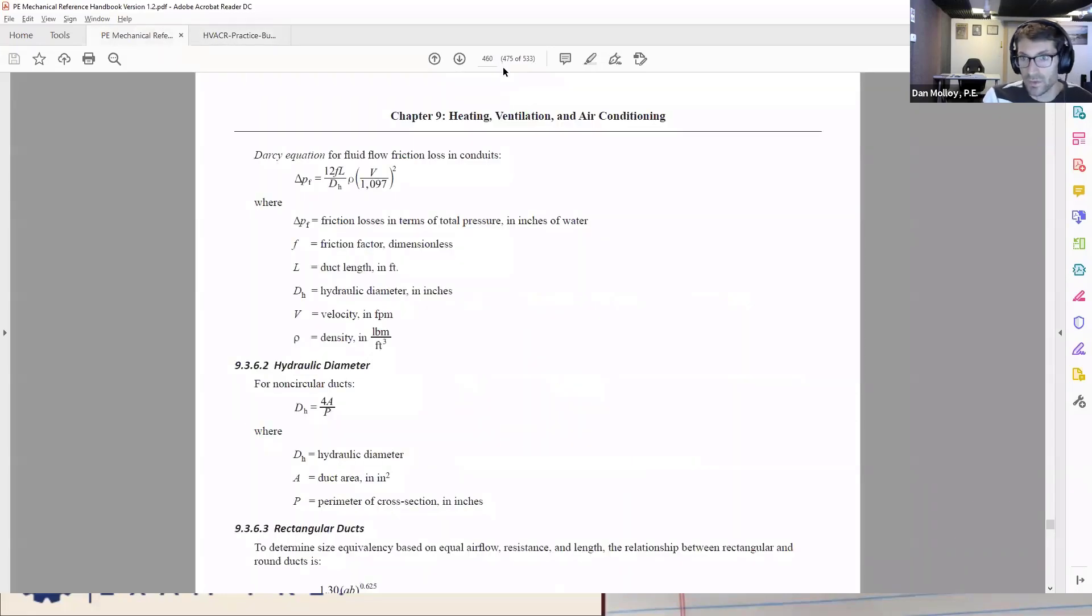So let's go straight to 460. Here's the equation. This says that the friction loss should be 12FL over hydraulic diameter times density times this term velocity over 1097 squared. And unlike most equations where we write out all the units and make sure everything cancels, this is one of those pre-formulated equations where we put everything in the specified units in the first place.